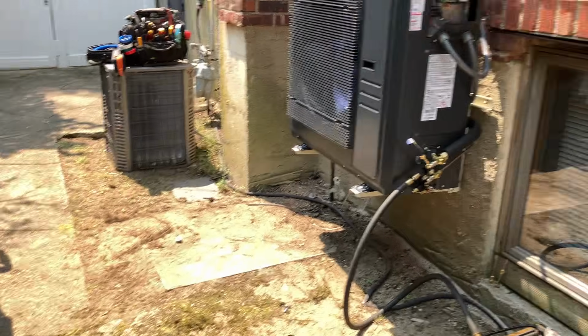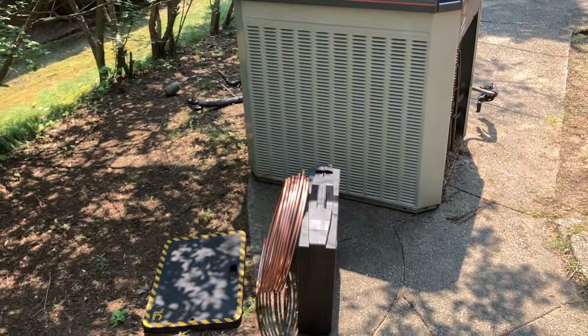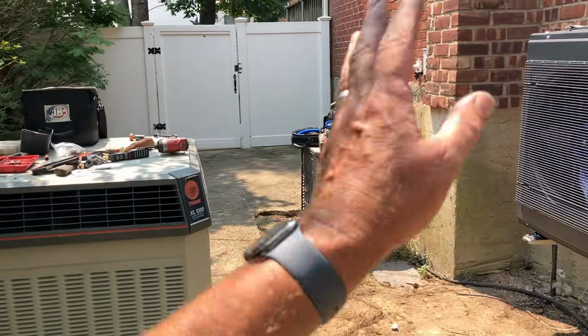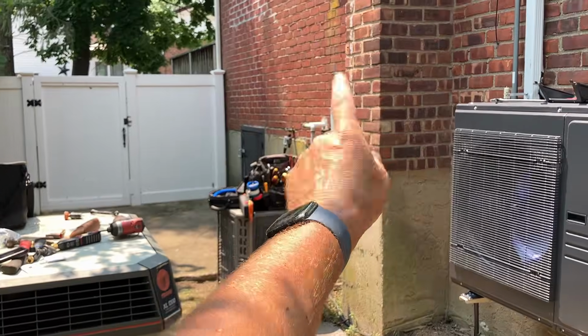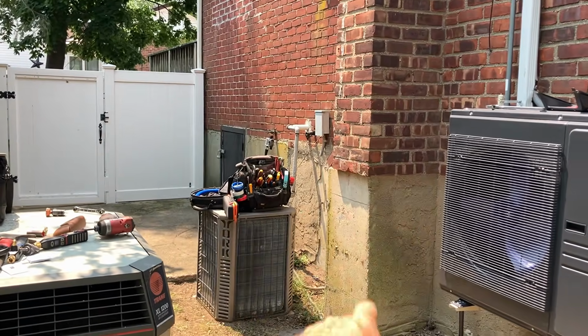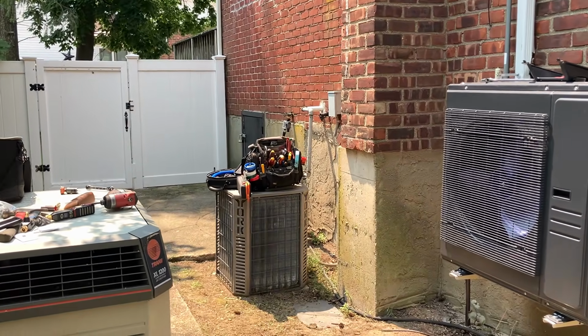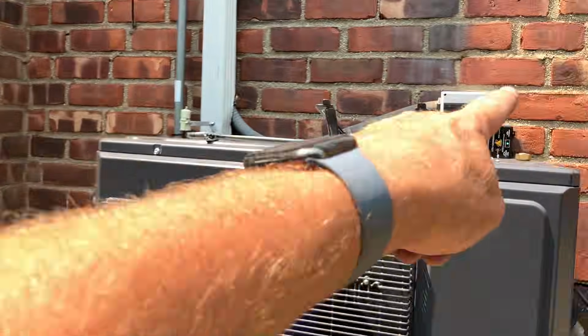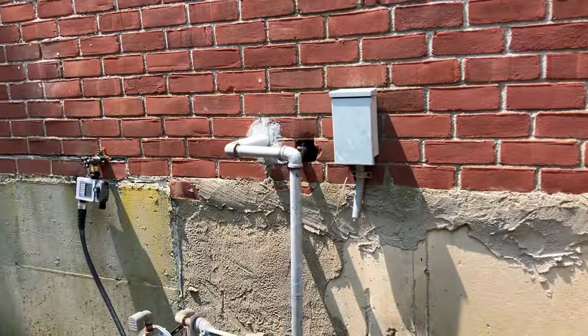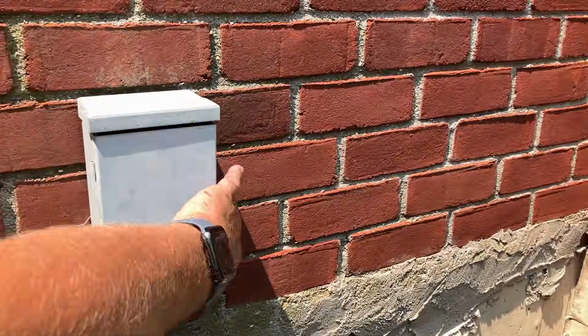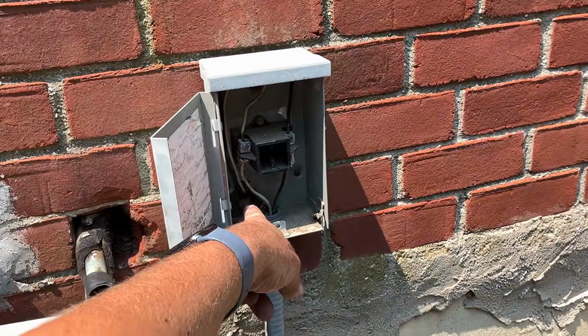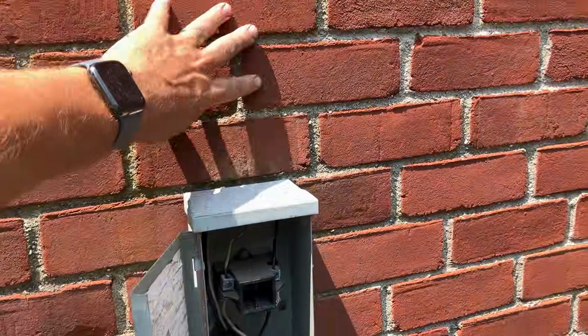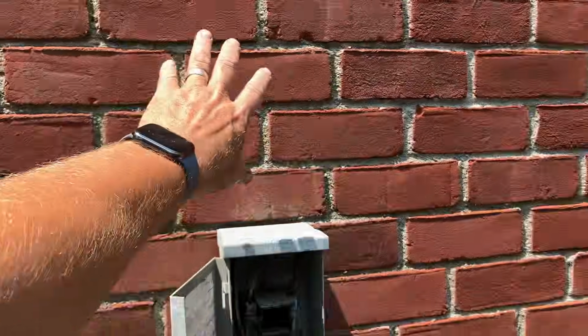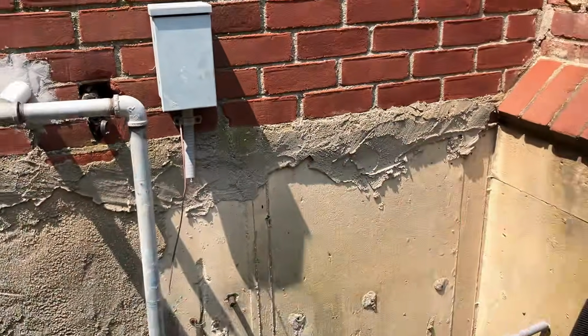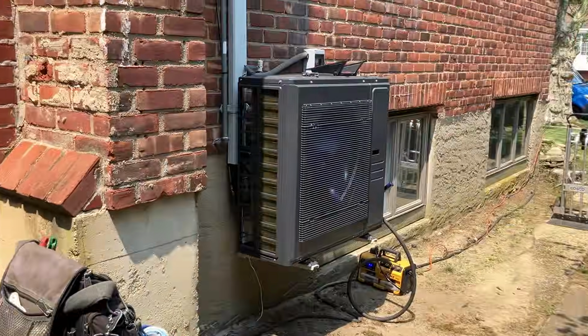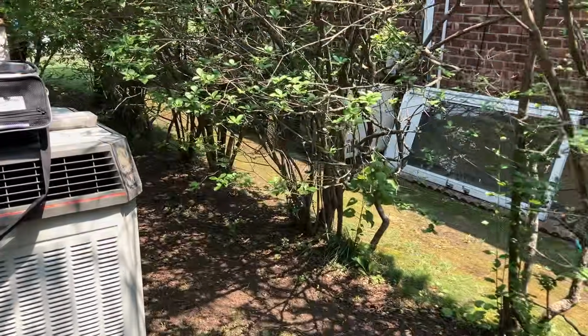You know what? Let me start putting some stuff away, like the ZoomLock, the 3/8 tubing. That's already disconnected, by the way. Cut the line set, cut the whip off the disconnect panel. I already sized up what I'm gonna need for that, so it lines up with this one. I'm just gonna get some conduit with a little junction box there and go up here and then mount that box at the same elevation as this right here. And plenty of room, perfect. It's gonna look really, really nice. Much better than what the neighbor has over here.